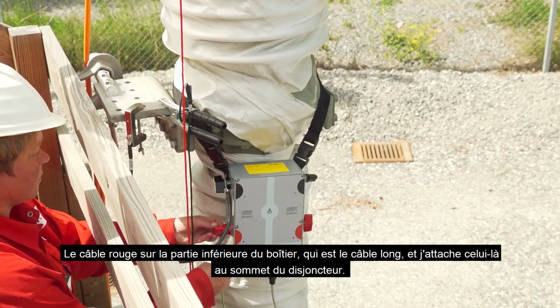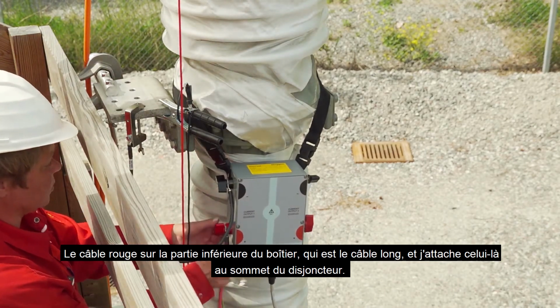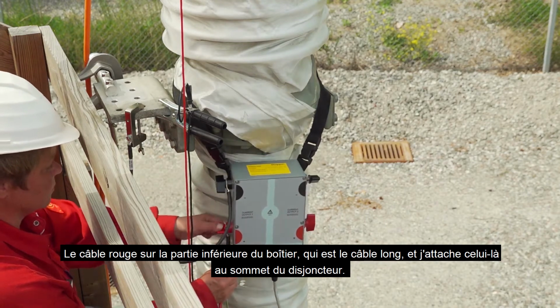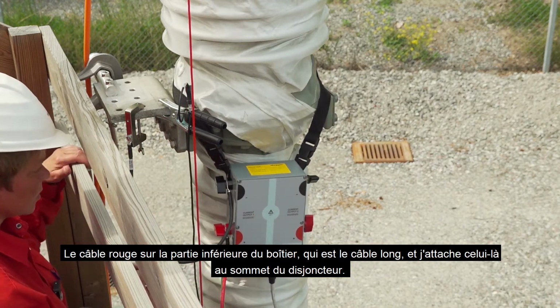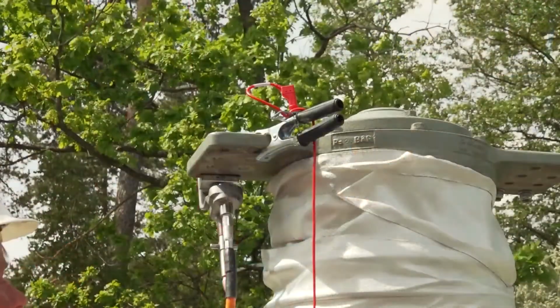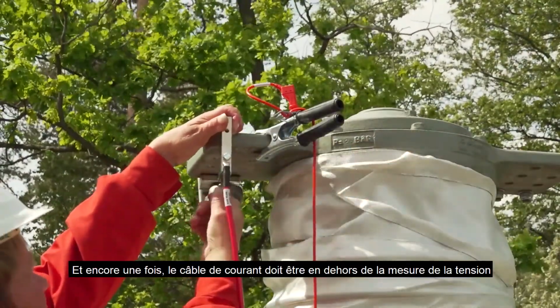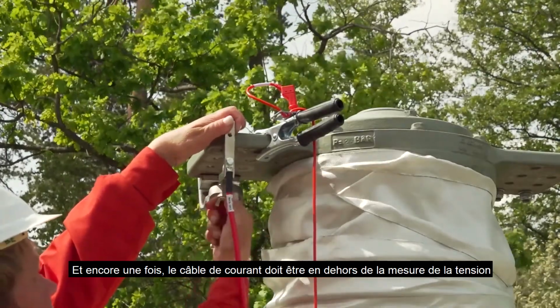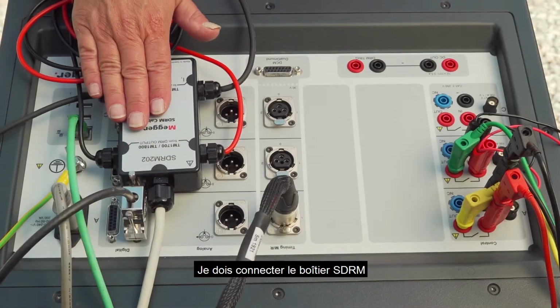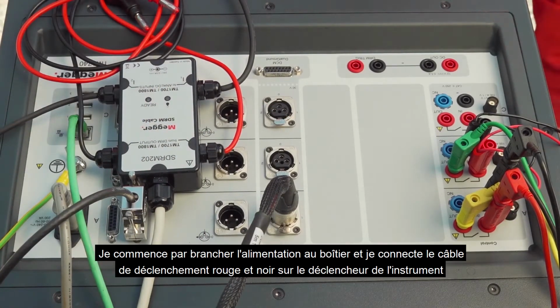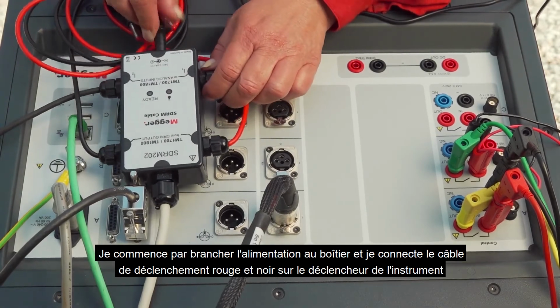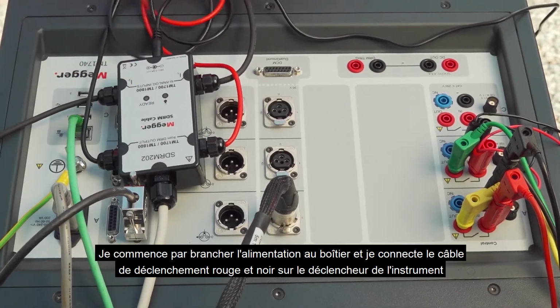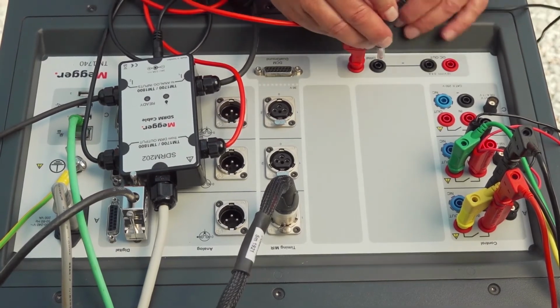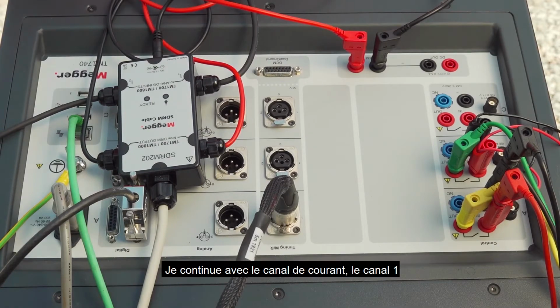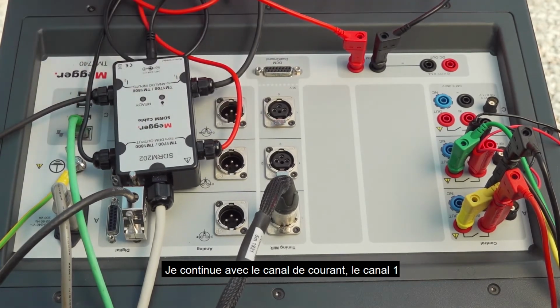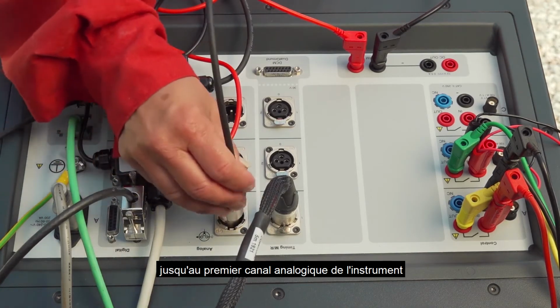The red cable at the lower part of the box, which is the long cable, and I attach that one at the top of the breaker. And again, the current cable needs to be outside the voltage sense. I need to connect the SDRM box. I start with connecting the supply to the box, and I connect the red and black trig cable to the trig of the instrument. I continue with the current channel, channel 1, to the first analog channel of the instrument.